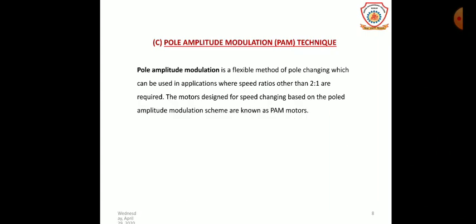The pole amplitude modulation method addresses the basic disadvantage of the other methods, which is the non-availability of smooth speed control. The ratio of the two speeds in this method need not necessarily be 2:1. Motors designed for speed changing based on pole amplitude modulation schemes are known as PAM motors.